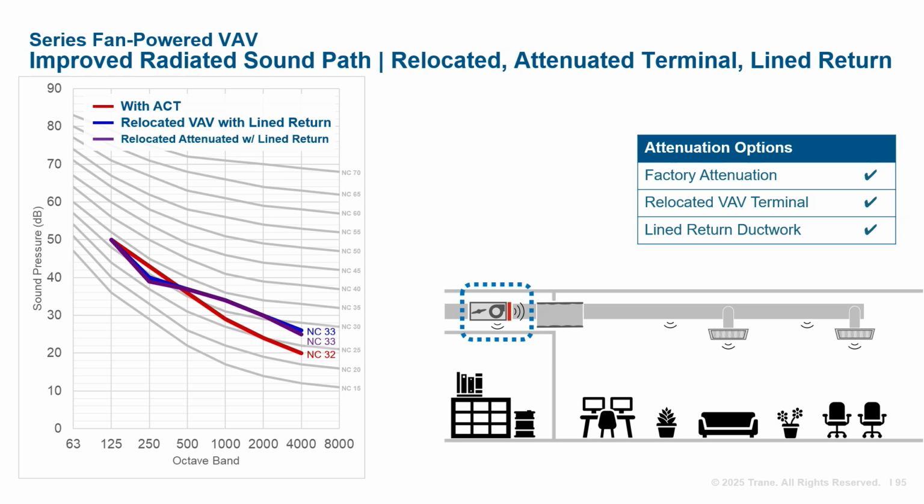NC 33 or 40 dBA, 51 dBC. You can see that the octave band is not exactly the same, but it's very close, and those details are lost in the simplification process. So why didn't the attenuated box provide better space sound?